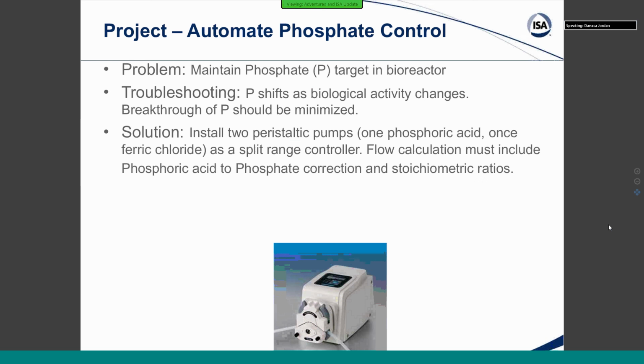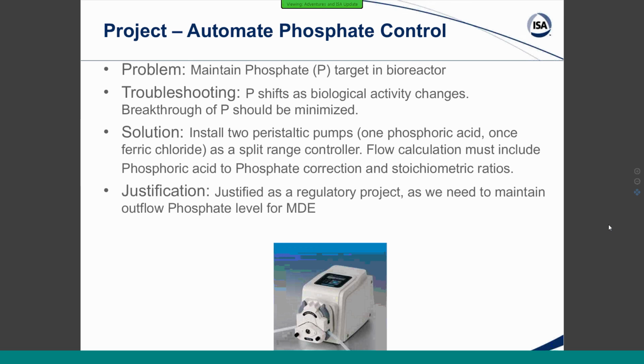So our solution is a very interesting split range controller. You can think of this as a hot water and a cold water valve that you're putting together to make warm water. In this case, we put phosphoric acid and ferric chloride in. One raises the phosphate level and the other one lowers it. It gets complicated. All of the calculations did have to include the phosphoric to phosphate and the stoichiometric ratios for the ferric chloride. So there was a lot that had to be included in that controller. But we did have very good results.